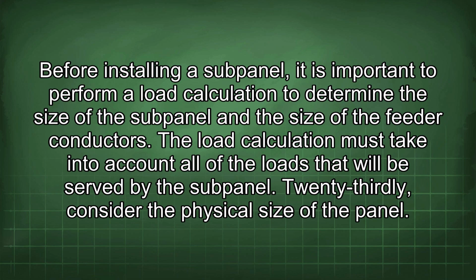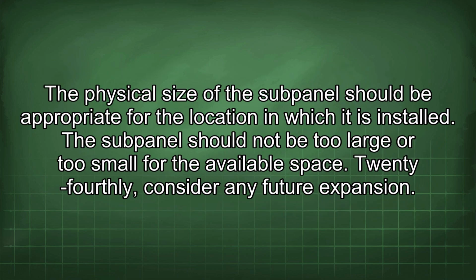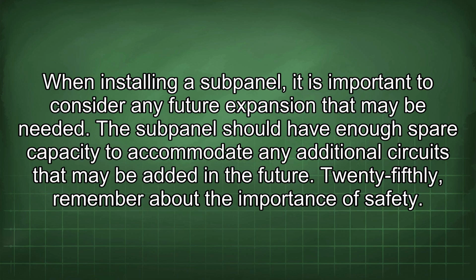23rdly, consider the physical size of the panel. The physical size of the subpanel should be appropriate for the location in which it is installed. The subpanel should not be too large or too small for the available space. 24thly, consider any future expansion. When installing a subpanel, it is important to consider any future expansion that may be needed. The subpanel should have enough spare capacity to accommodate any additional circuits that may be added in the future.